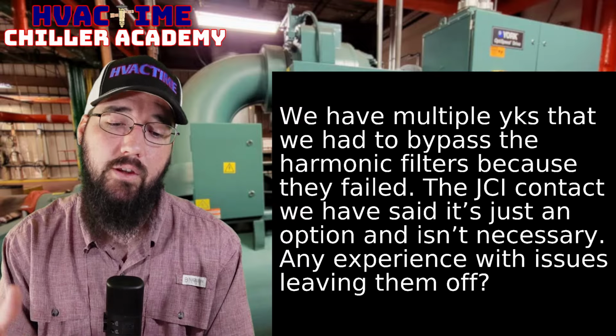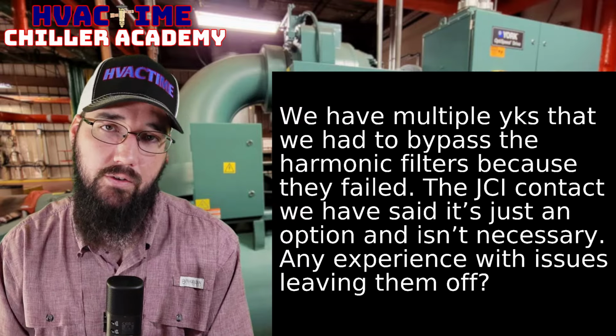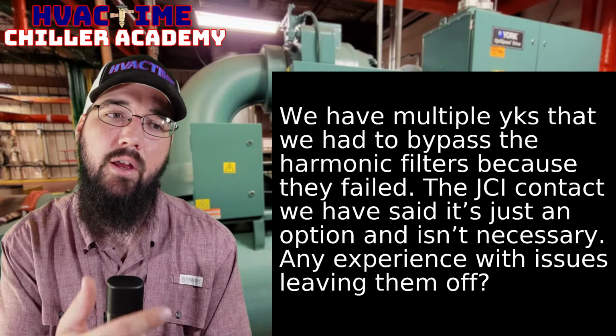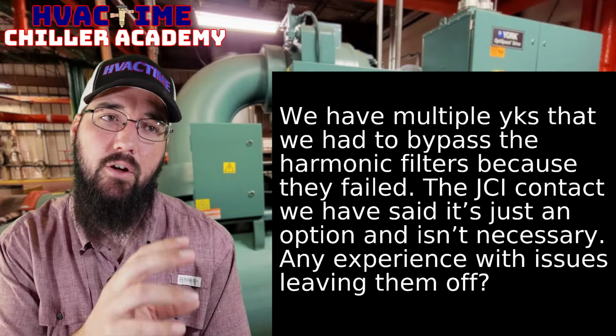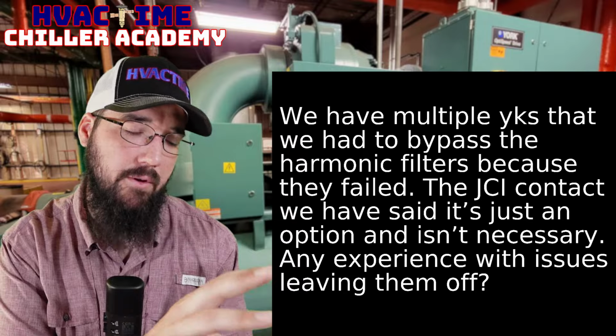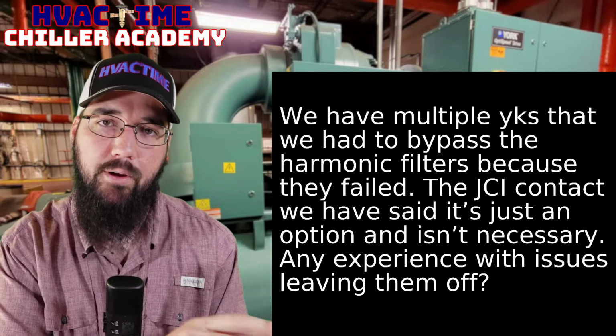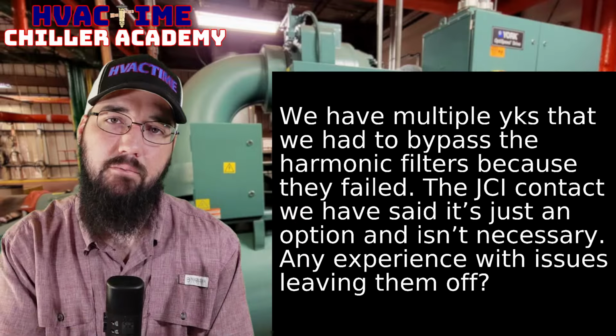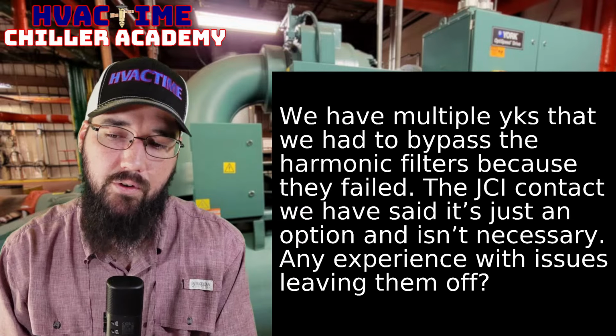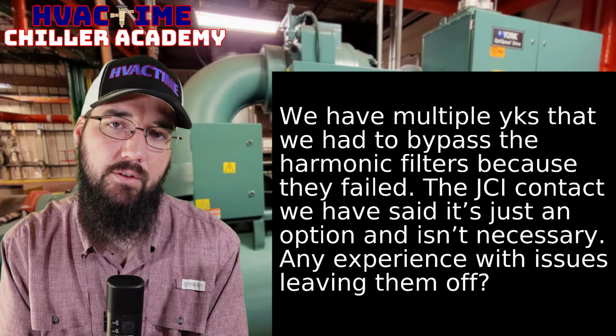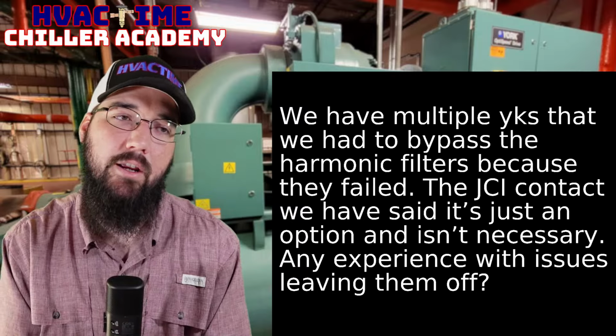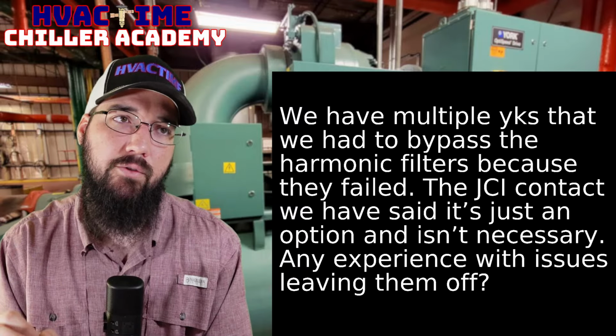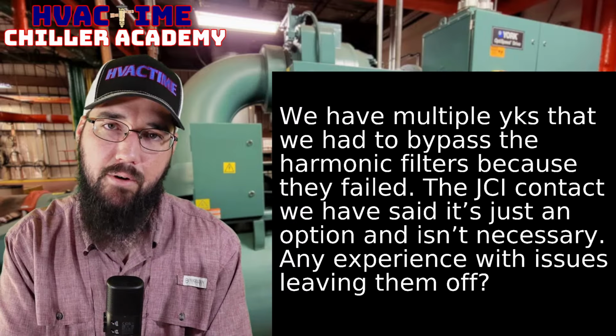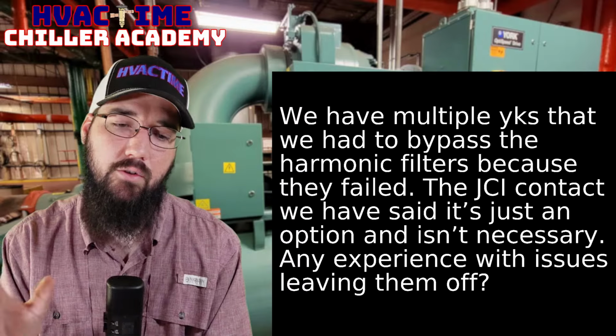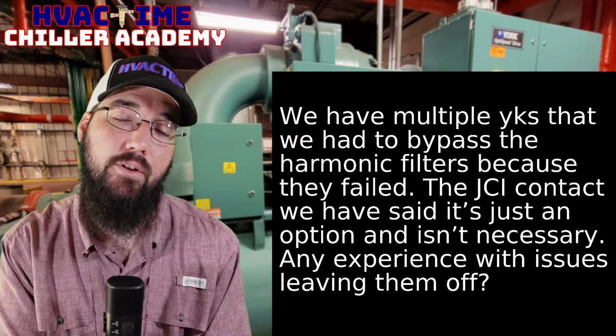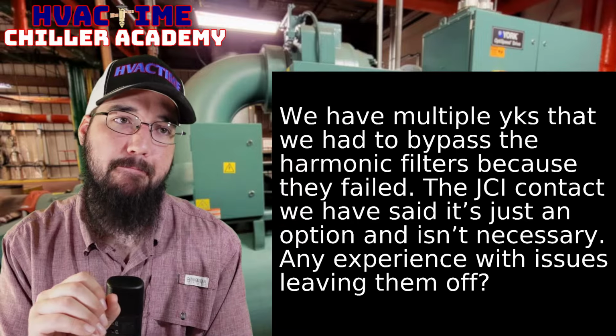I know on the older ones, you remove the components themselves from the electrical circuit, bypass it on that scale, and then you can disable it in the configurations on the OptiView control panel. You can just set it to not installed, basically, and then remove the components electrically, and it's isolated from the system. At that point, it could have just been shipped without it. The new versions of those drives, like I said, on the mag bearing machines, I don't think that's an option. Those are a part of the drive assembly as a core, right? So just something to be aware of.